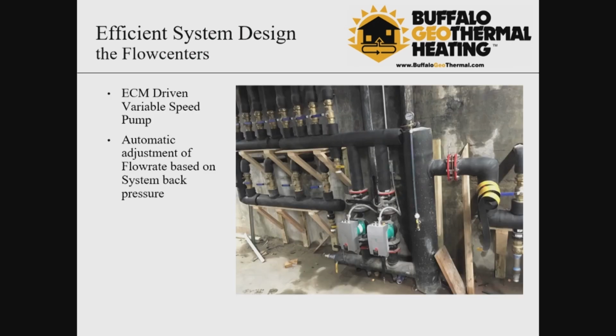On the southeast and southwest side, which were marked in orange and green on the previous slide, we opted for a dual pump flow center with ECM-driven variable speed pumps. Each of these pumps can handle the load of the entire system it operates, and the second acts as a backup. These pumps are PID controlled with an automatic flow rate adjustment based on the back pressure of the system. So when a heat pump turns on, it opens up its zone valve, the pump will recognize this and rev up the flow rate. Again, increasing pumping efficiency.